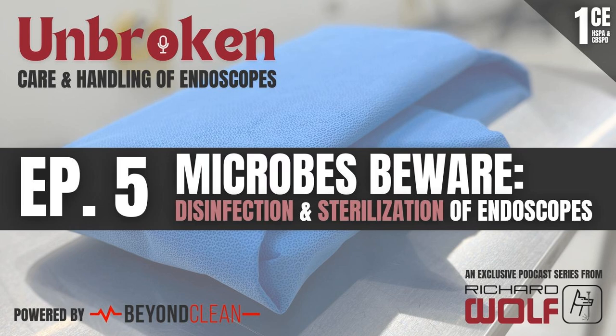If I can add one feedback to that too. Yeah. So I didn't answer, Hank, your second part of your question, the risks. So really, there's distinct risks between doing high level disinfection and sterilization. Obviously, the exposure of the high level disinfection to our technicians, versus low temp, you still have some hydrogen peroxide exposure potential, but it's much lower risk than a splash of HLD to your face, depending on if you're doing automated or manual processing. And then versus steam, you're just messing with the heat, and whether the device can withstand it.